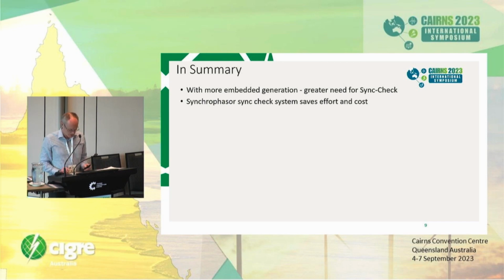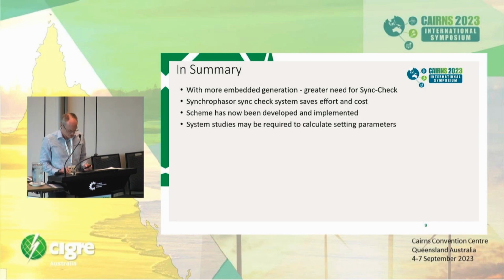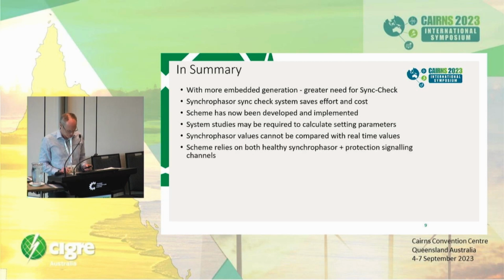In summary, with more embedded generation, there is a greater need for synchronism check associated with auto-reclose. Synchrophasor synchronism check systems save effort and cost. The scheme has been developed since the initial design and has now been deployed and implemented over the last few years. System studies may be required to calculate some setting parameters, particularly for voltage transient conditions. Synchrophasor values cannot be compared with real-time values, so the scheme relies on signal alignment and dedicated logic. It also relies on both healthy synchrophasor and protection signaling channels.